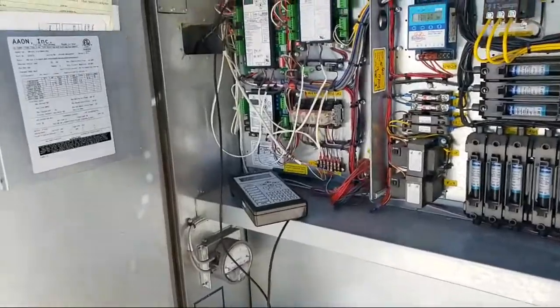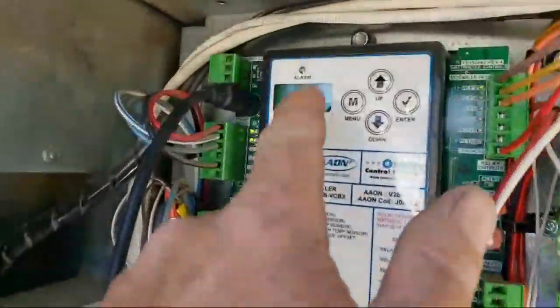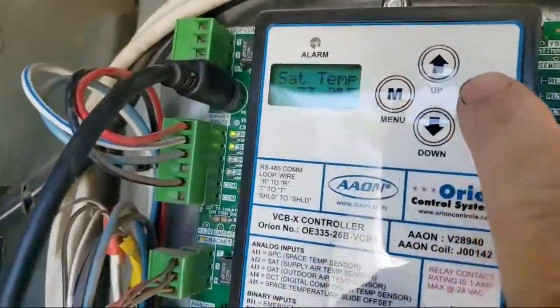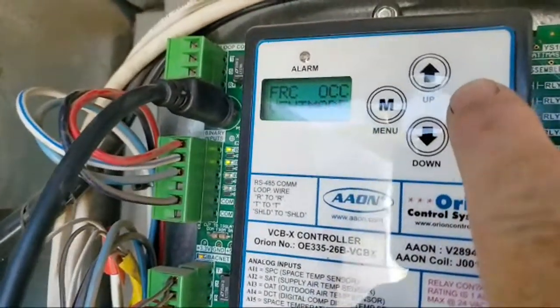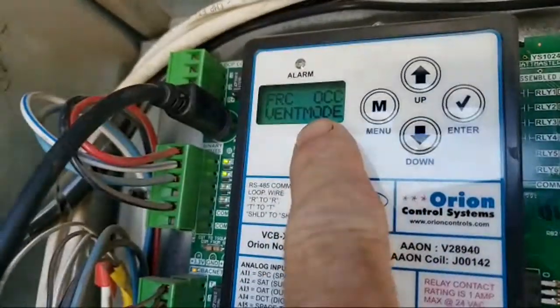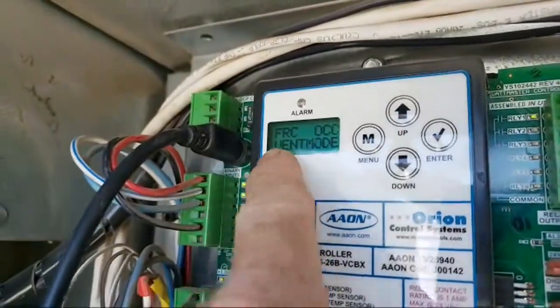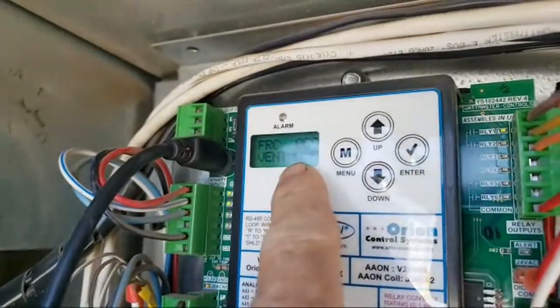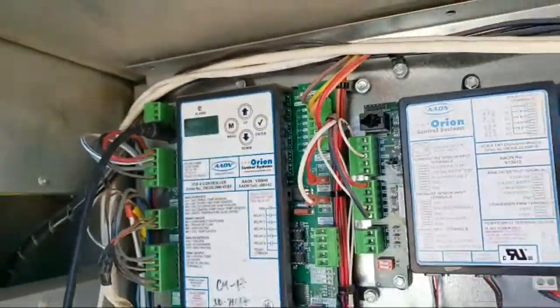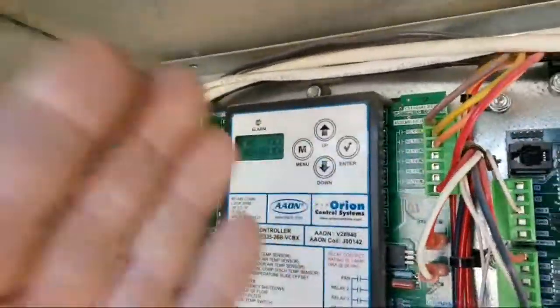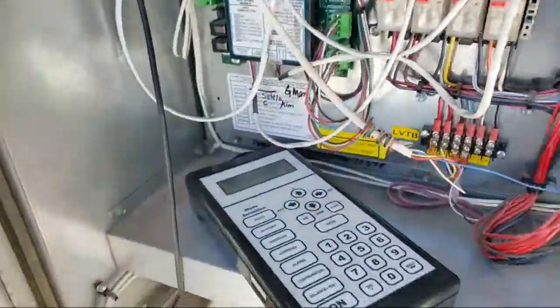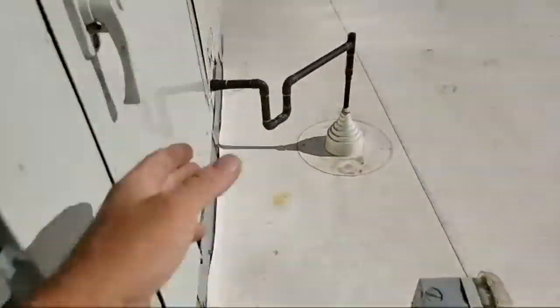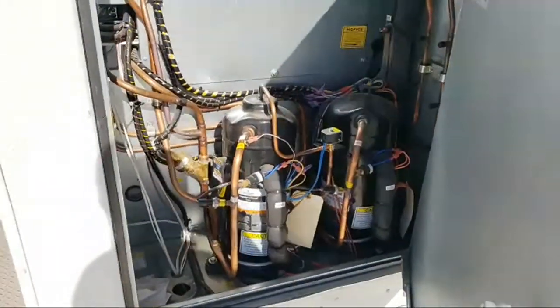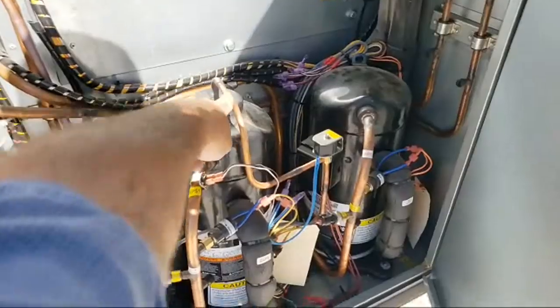So I came here the other day, and when it shows you your modes here, it cycles through. Vent mode now, but it's been stuck in RH reheat, which is relative humidity. It's under that control loop at that moment. It's trying to reheat. And what this system has is two compressors. One of them has the unloader on the top of the scroll, so there's an unloader valve, 3-port scroll.